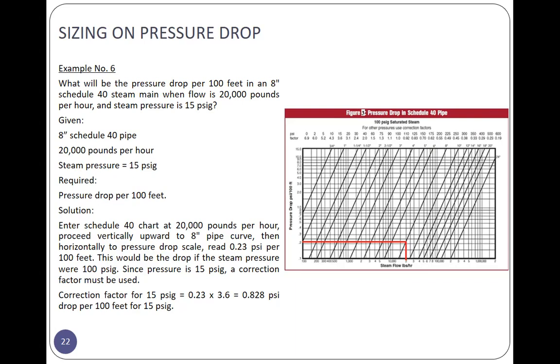Solution: enter the schedule 40 chart at 20,000 pounds per hour. Where is the 20,000 pounds per hour? This is 10,000, this is 100,000. So this is 20,000. And go vertically upward to 8 inches. And 4, 5, 6, 8, 10. So there. Then draw a line over to here, and the reading is 0.1, 0.2, 0.3. So this is 0.23 PSI per 100 feet.